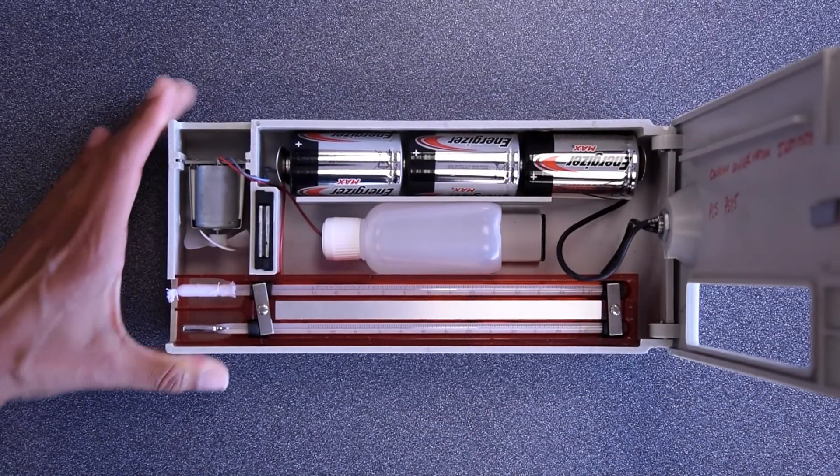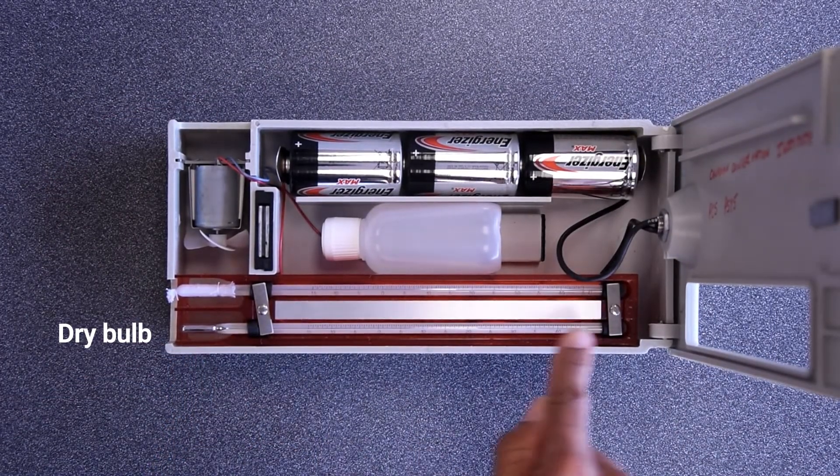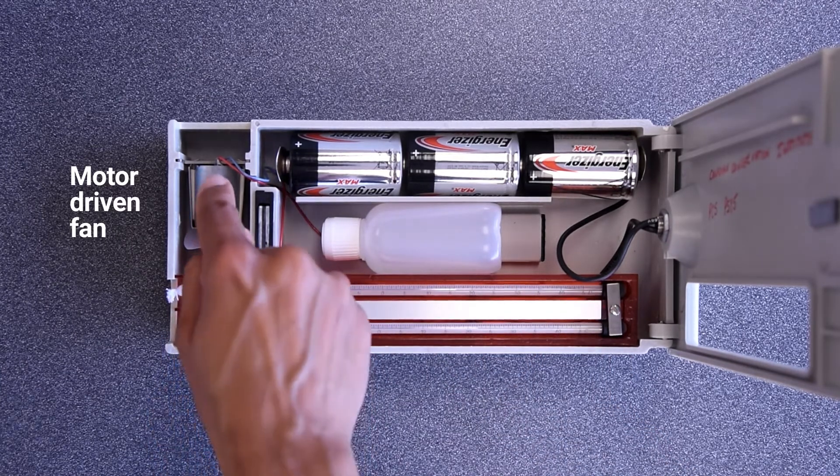This psychrometer is a battery-powered aspirating psychrometer. It has a dry bulb thermometer that is kept dry, a wet bulb thermometer with a sock that is wetted, and a motor-driven fan.